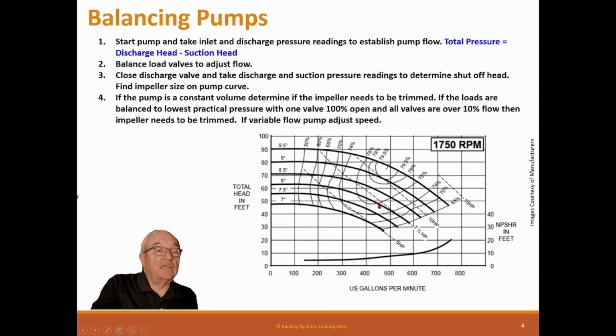Now, many times the design may be here. Your design may be 300 GPM at 70 foot of head, and you don't actually have that. When you go out and measure it, you only got 60 foot of head, so it'll actually do more flow. It'll do 450 or something like that, which means if your balance doesn't actually take some of that out when you do the field balance, you actually cause back pressure in the system, and you will lower flow. And that's why I always say try to set the pump up a little higher so you got some room to back up that pressure up the curve so it'll work. So this is how we find out where we're at.